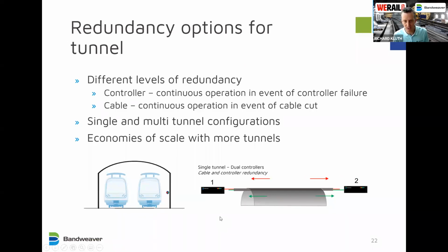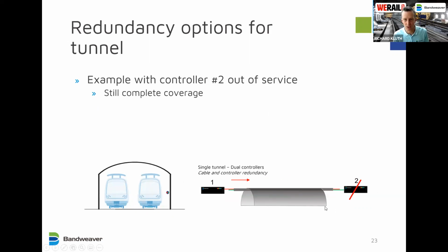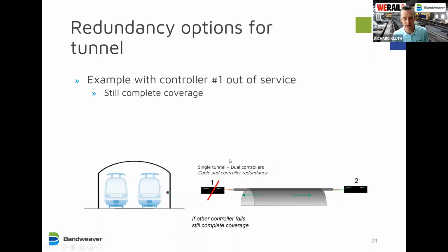So when both systems are operating, you can see the red pulse travels to the end of the fiber, reflected light goes back to number 1. Similarly, number 2 travels to the end of the fiber, comes back. You have full coverage on the tunnel from both controllers. If controller 2 was taken out of service, you see controller 1 would still send the light to the end of the tunnel. You have absolutely full coverage while the system could be under maintenance or repaired. Similarly, if controller 1 is taken out of the loop, you have full redundancy. So in this scenario, it's not that different from typical system redundancy, but you notice in this scenario, we've put them at either end of the tunnel for this specific configuration.